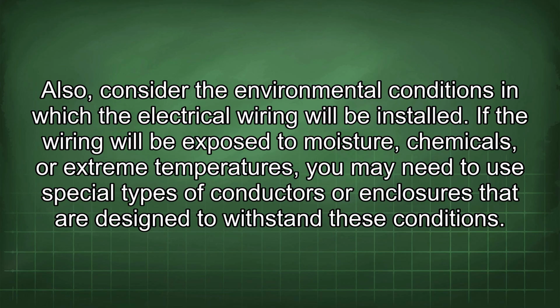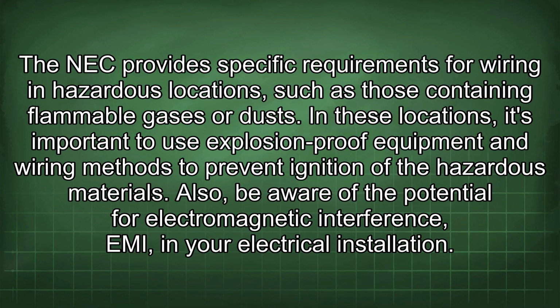Also, consider the environmental conditions in which the electrical wiring will be installed. If the wiring will be exposed to moisture, chemicals, or extreme temperatures, you may need to use special types of conductors or enclosures that are designed to withstand these conditions. The NEC provides specific requirements for wiring in hazardous locations, such as those containing flammable gases or dusts. In these locations, it's important to use explosion-proof equipment and wiring methods to prevent ignition of the hazardous materials.